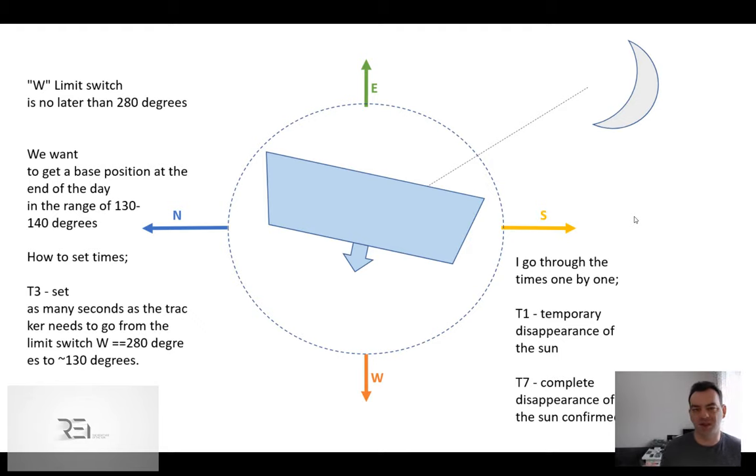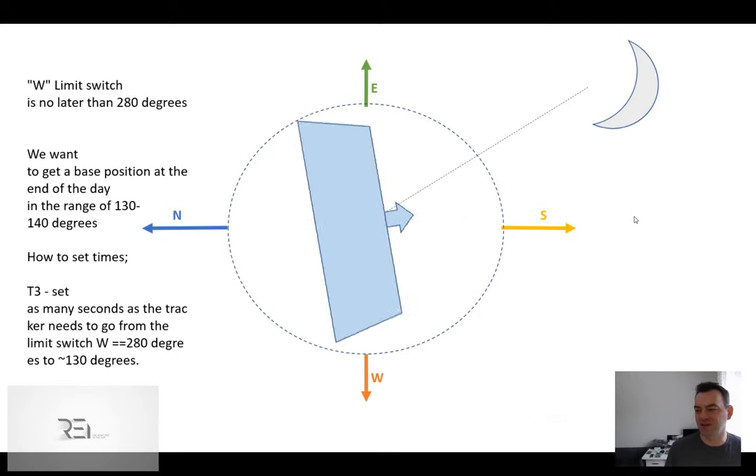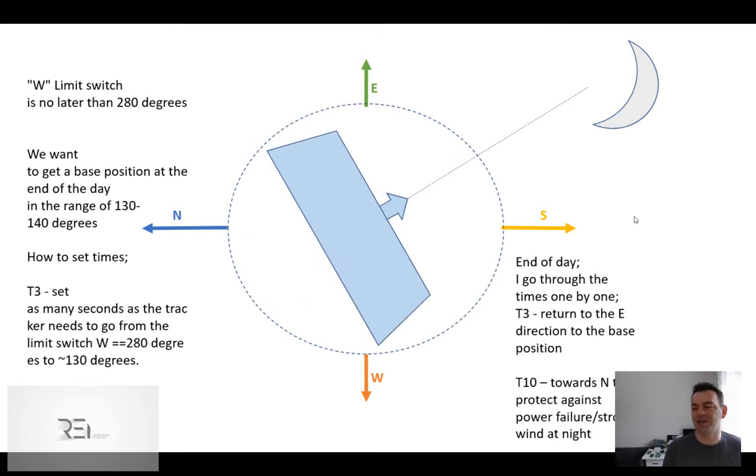T7 doesn't have to be so big. You can put there 1000 seconds or maybe less, and that will be enough. But T1 should be as big as possible, of course not longer than the whole night because you want to be prepared for the next day. Once T1 is finished and T7 is finished, then you set back to the standard procedure.